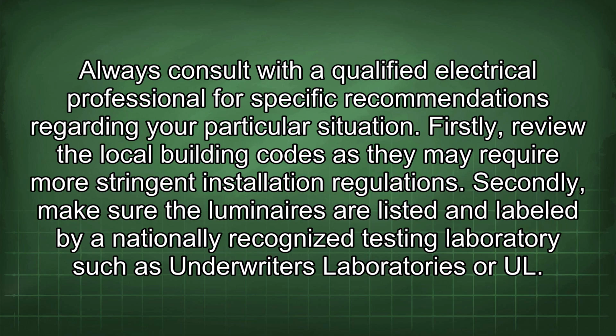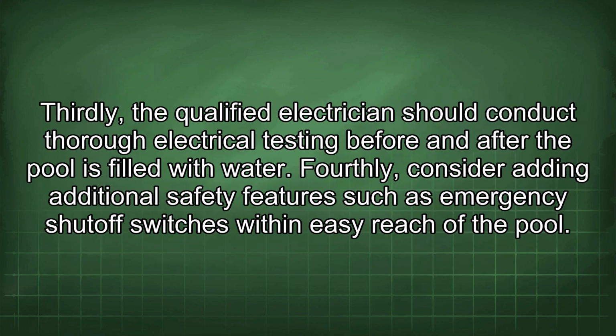Firstly, review the local building codes as they may require more stringent installation regulations. Secondly, make sure the luminaires are listed and labeled by a nationally recognized testing laboratory such as Underwriters Laboratories, UL. Thirdly, the qualified electrician should conduct thorough electrical testing before and after the pool is filled with water. Fourthly, consider adding additional safety features such as emergency shut-off switches within easy reach of the pool.